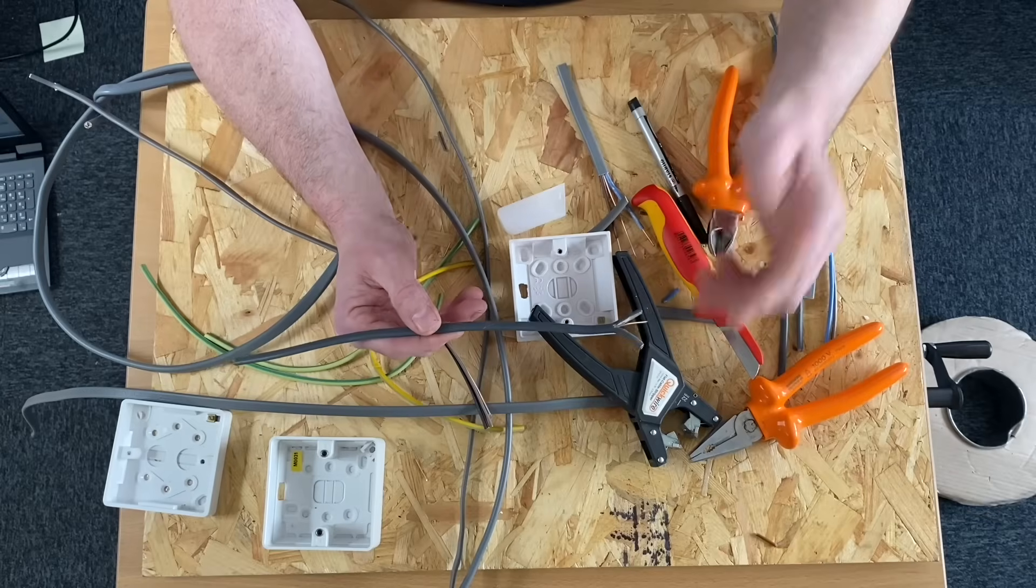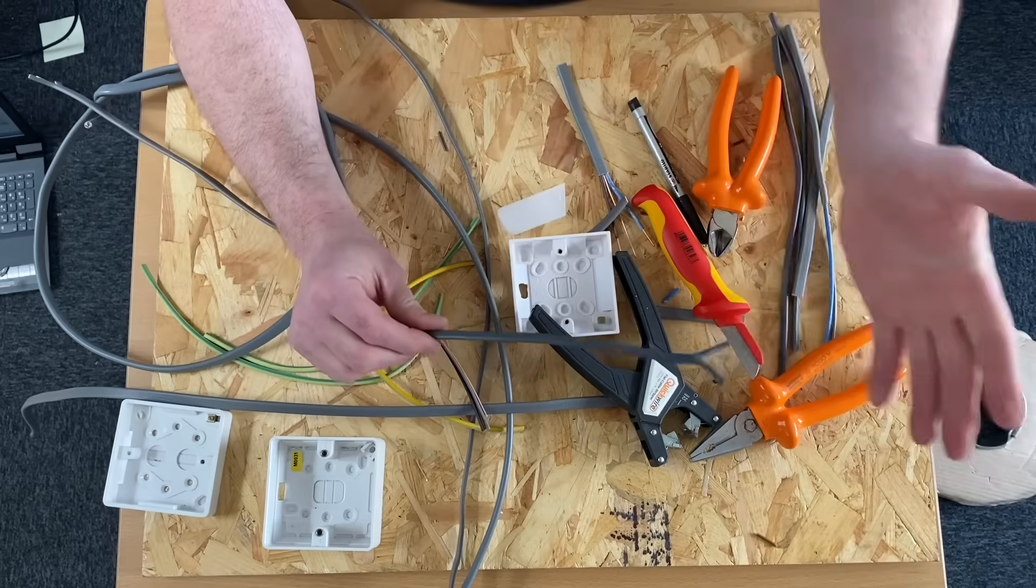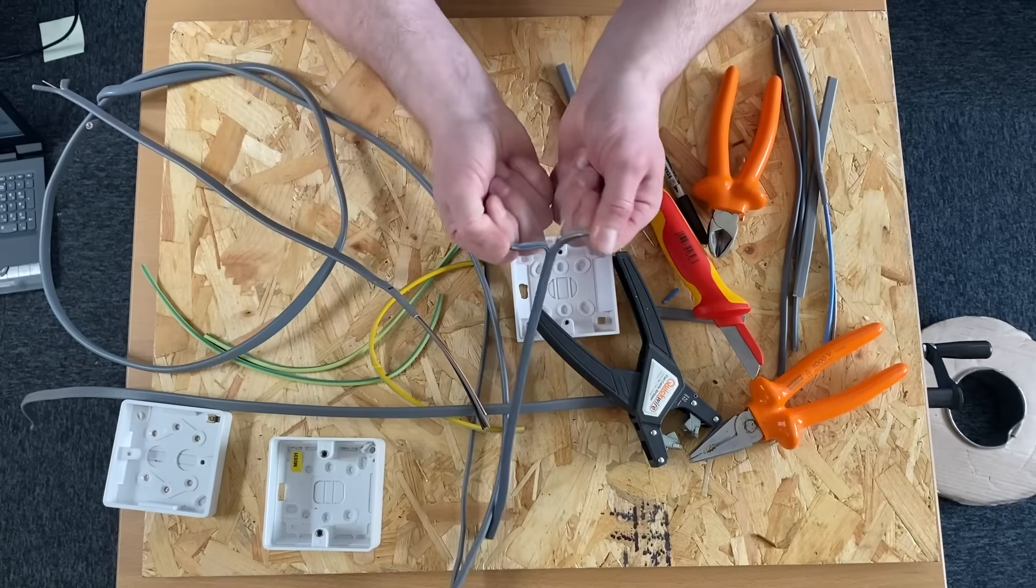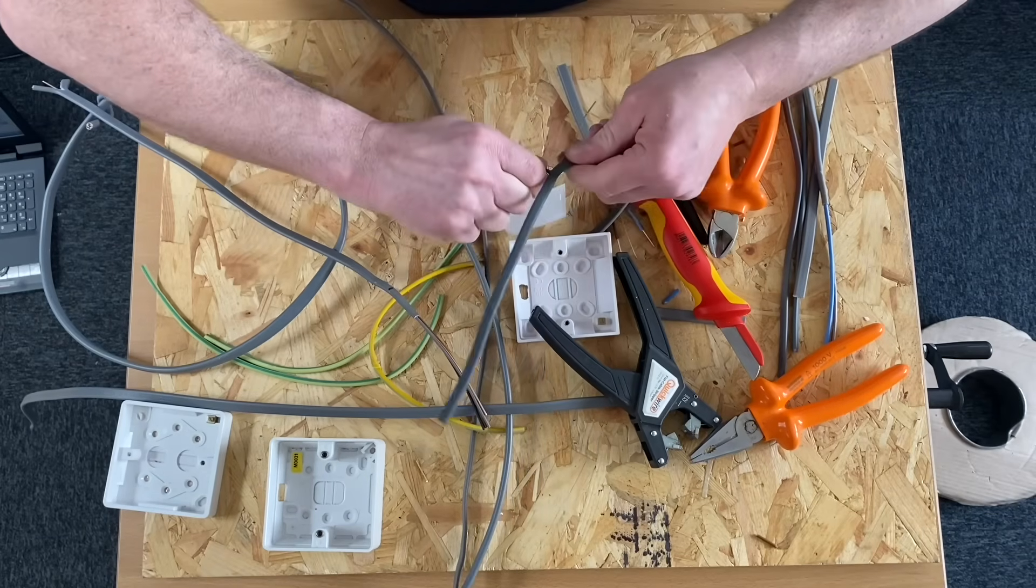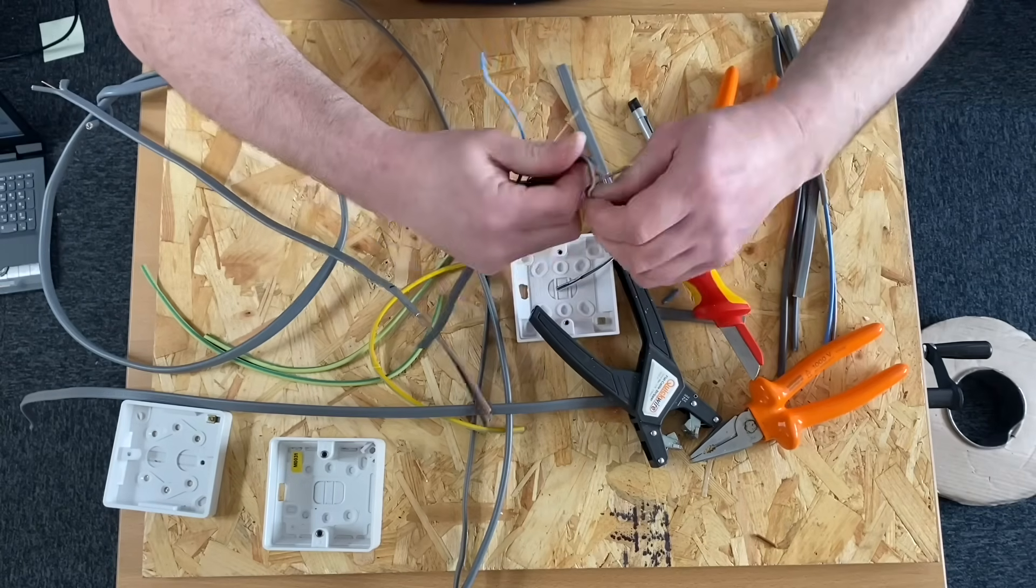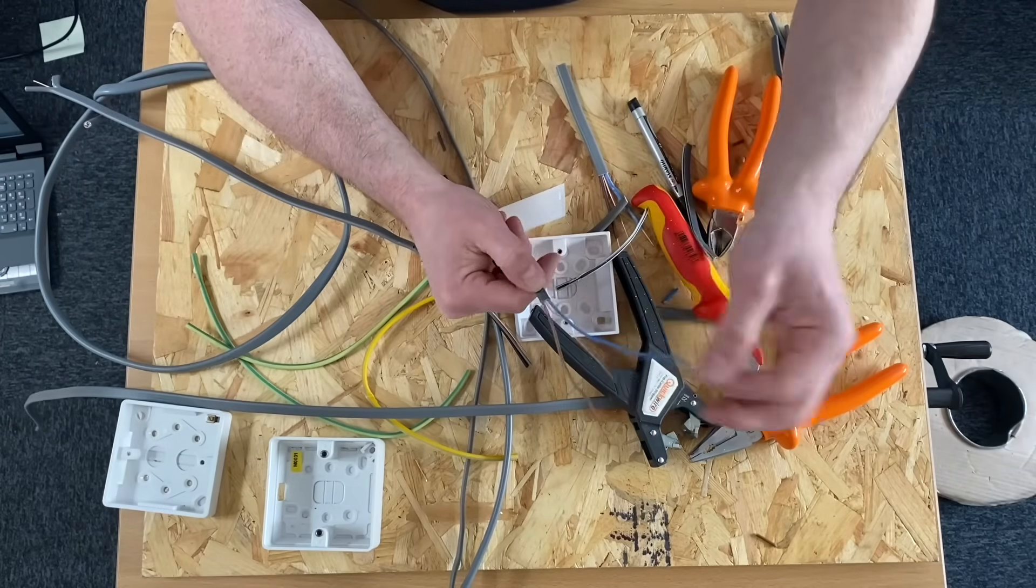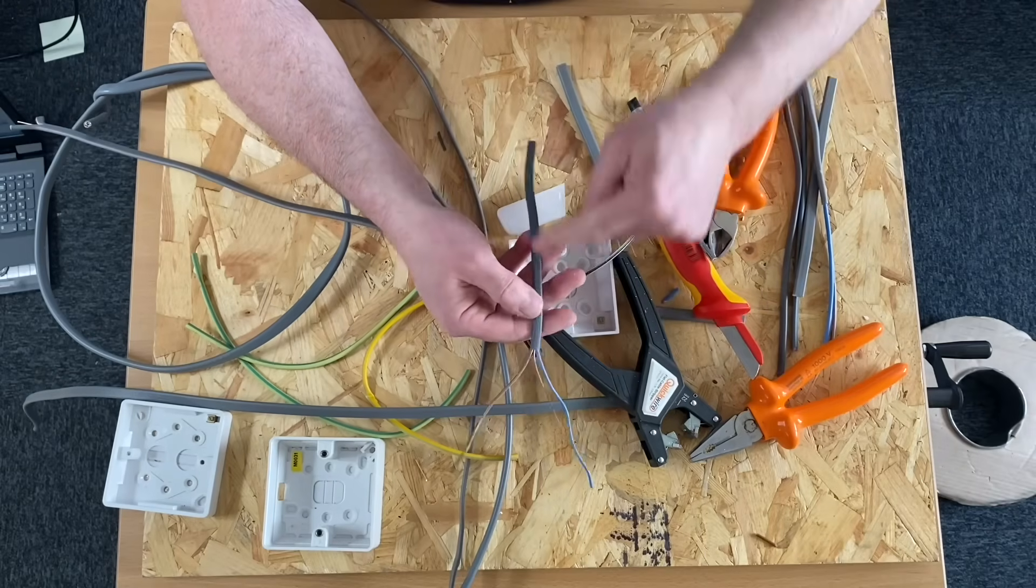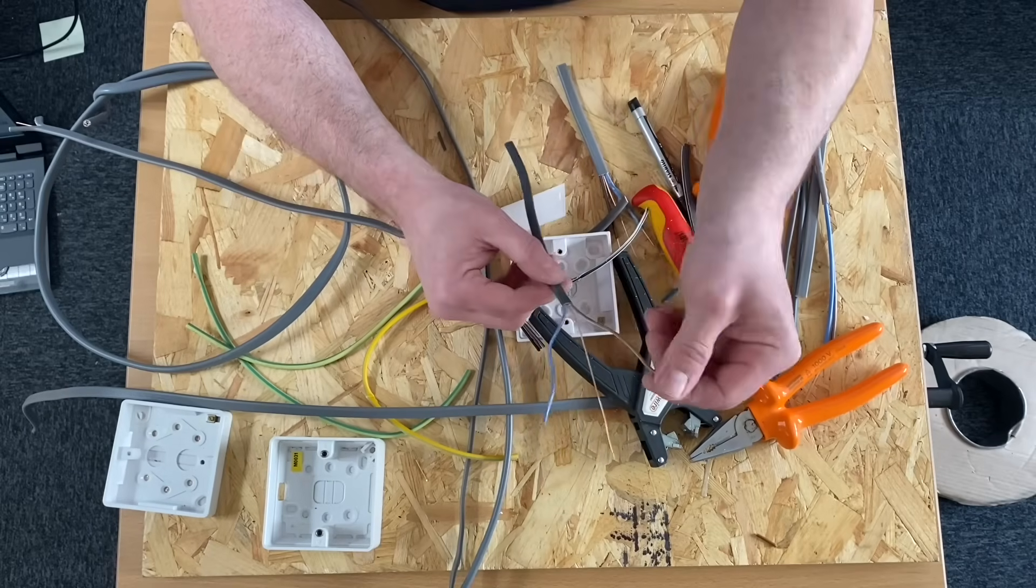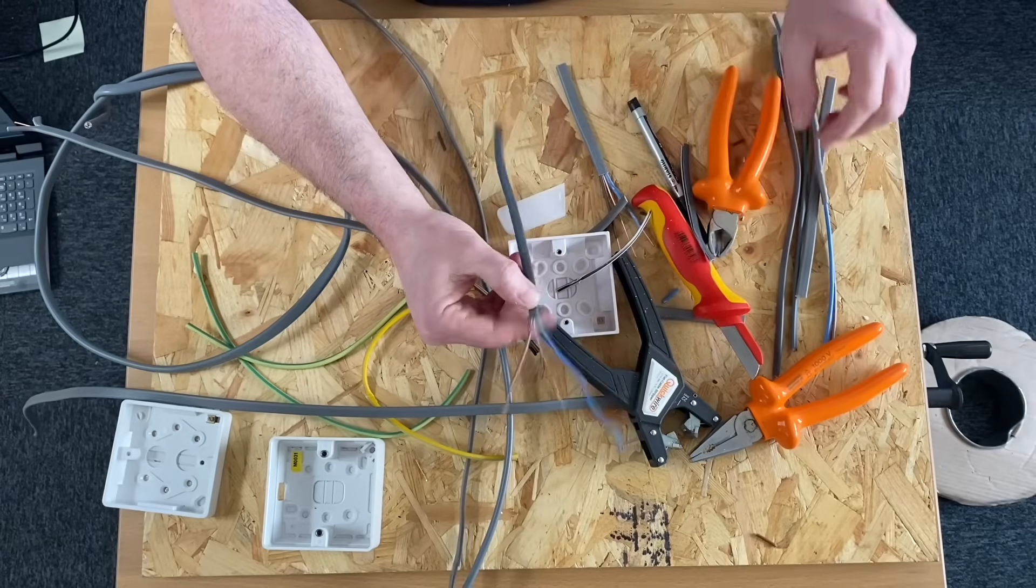And they've pulled the CPC out of the cable itself. And they've brought the CPC to me and said, what do I do now, Gary? Well, you unclip your cable and you replace it back onto the board. You know, get a lot of fuss and moaning at that stage. So we come up with a technique of actually holding our live conductors and rolling it out across our knuckles until we get down to the area in which we need to pull the actual mechanical protection off. So that meant that we didn't accidentally pull the CPC out. Now I can't suggest in the real world that I've ever not pulled against the CPC down to my area, which I've scored in order that I can actually break away the mechanical protection. So that's why we do that. And that's why I always hold the two live conductors and leave the CPC alone and don't pull against it.